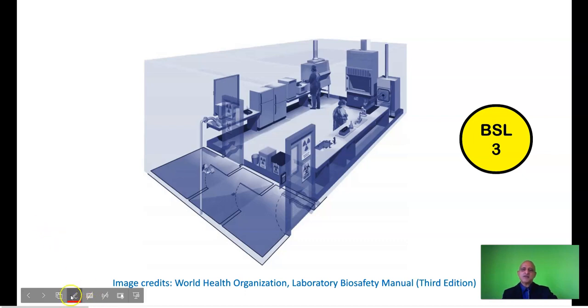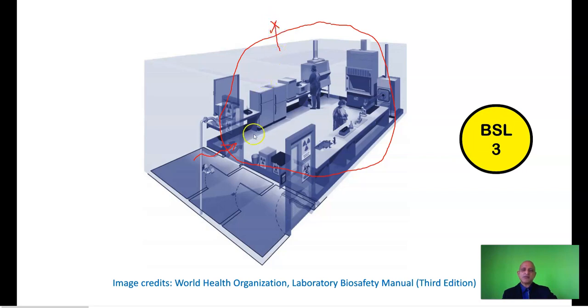So what changes in the BSL3? Let us look at it in detail. Okay, the first aspect is the directional airflow. The BSL3 laboratory is maintained at a negative pressure with reference to the outside air. So which means that the air within the system has to be evacuated, and this forms the principle for directional airflow. Now the air enters through this laboratory and it's discharged via the hard duct, and it also may be discharged via other vents, and it is discharged into the environment via the HEPA filters, which allow the flow of the air but not the flow of the pathogens into the environment, and this accords a level of protection of the environment. Now as you can see, the autoclave has been shifted into the laboratory facility.